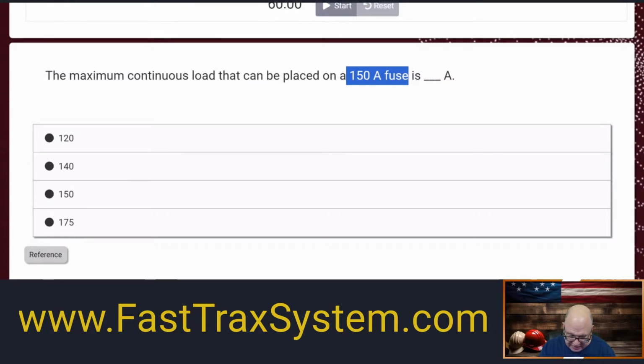Now, how do we know this? I can take that 120 and multiply it by 1.25, which is the multiplier that we use, and that gives us 150. So that 120 of actual load multiplied by 125%, that's where we get the 150. So remember the reciprocal, depending on what you're presented with. If you're presented with the actual rating of the device, then you multiply it by 80% to find out what the actual continuous load is that can be on it. And it's just an exercise we do of taking that actual load at 125% and then sizing.